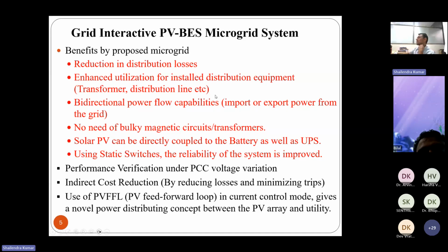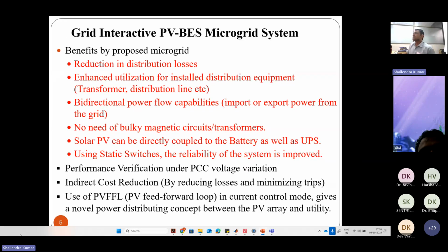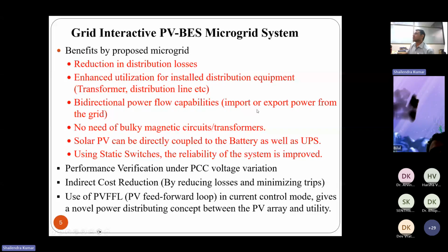Enhanced utilization of installed distribution equipment. Bidirectional power flow capability is there, meaning whenever sun energy is more than the load demand, the rest of the power can be fed to the grid. Whenever the solar energy is down, at that moment we can take power from the electricity grid, so bidirectional power flow is possible. No need of a bulky magnetic transformer, since we have used a simple bidirectional converter at the battery side, so this high frequency transformer is reduced. Solar PV can also be directly coupled to the battery as well as UPS.